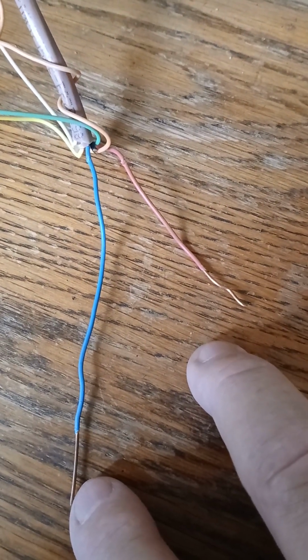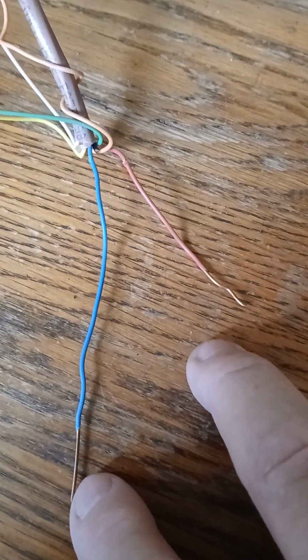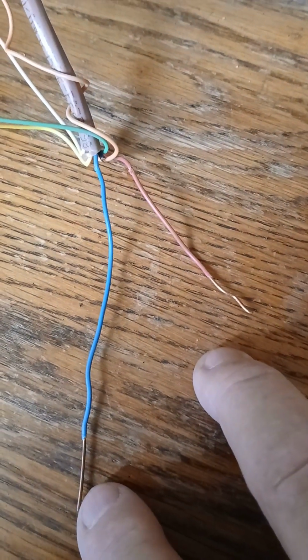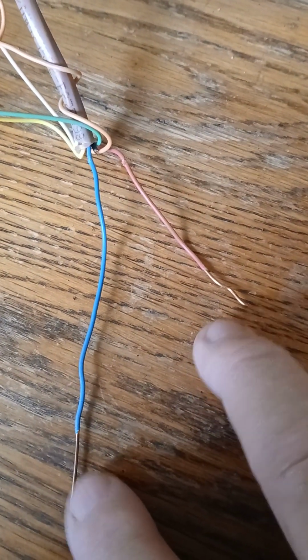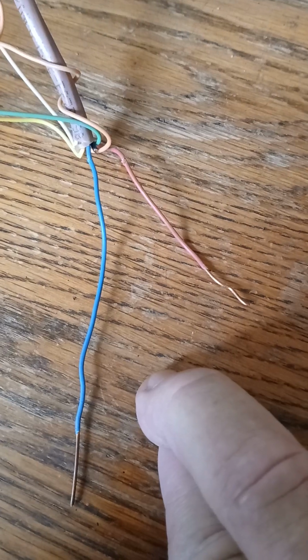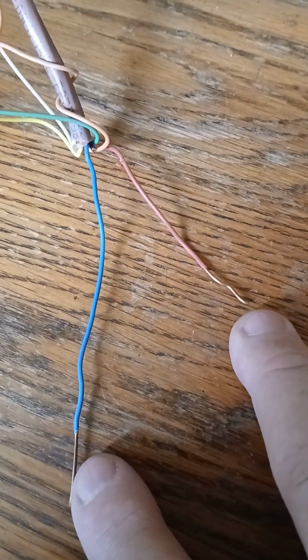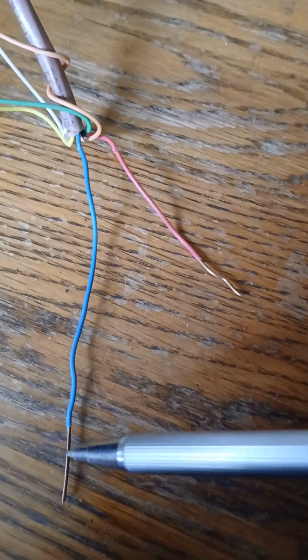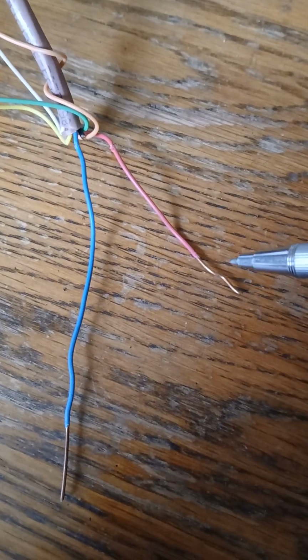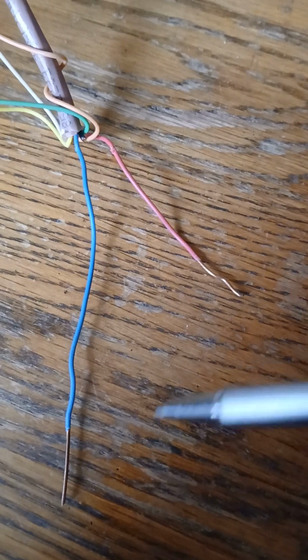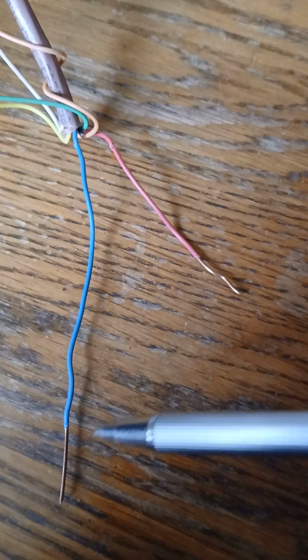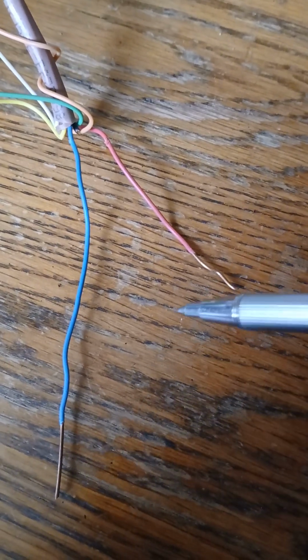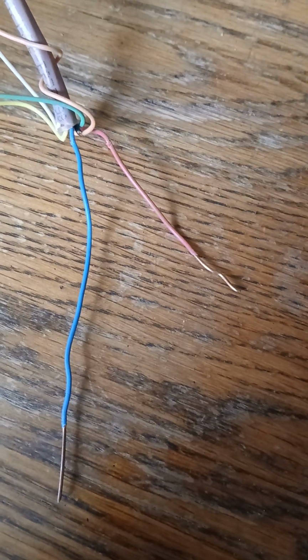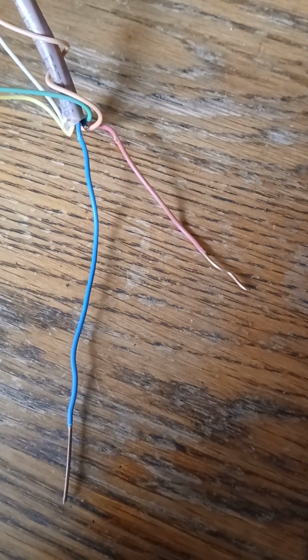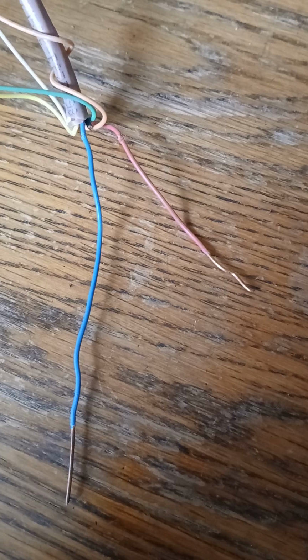It depends on if you have another transformer on the truck, how far the supply house is, etc. So just be cognizant of the fact you do not want to take these two wires and do this. When I say that, I'm not referring to the blue part or the red part. I'm referring to the metal, which looks copper-esque. Do not touch the red and the blue on the exposed wire while the system is energized with voltage. Otherwise, you may blow your transformer.